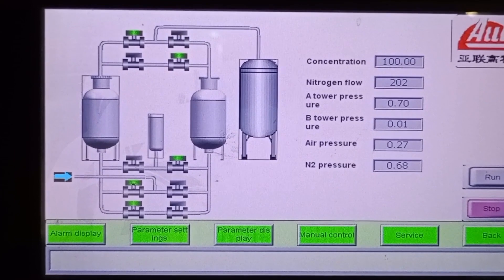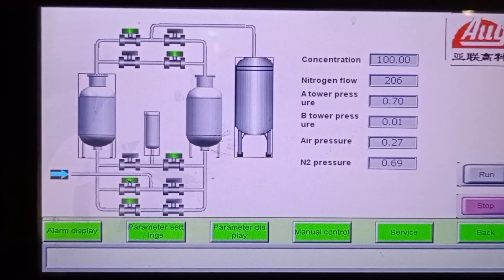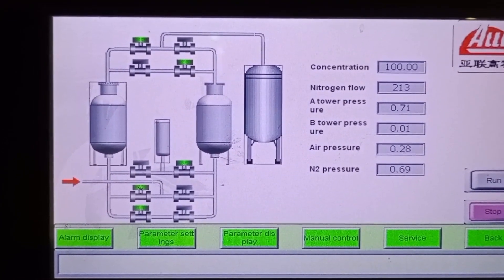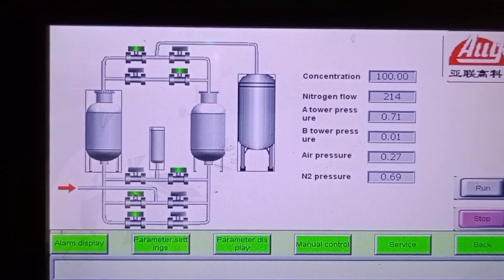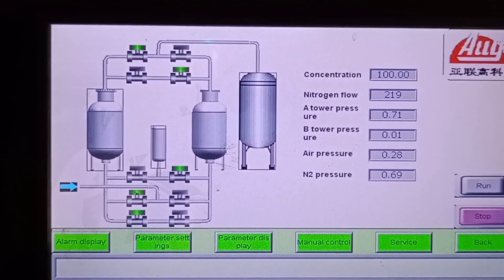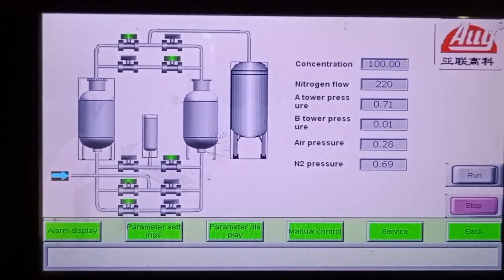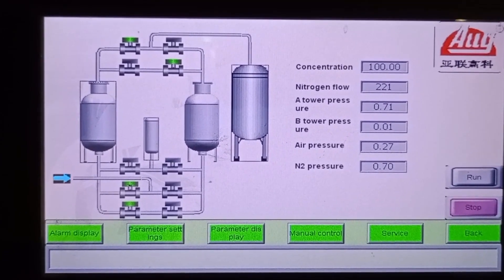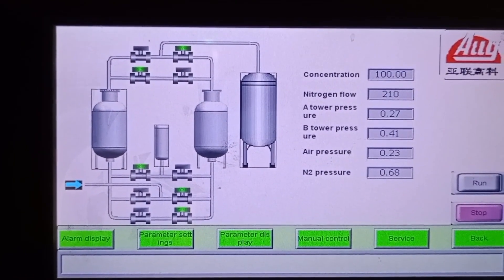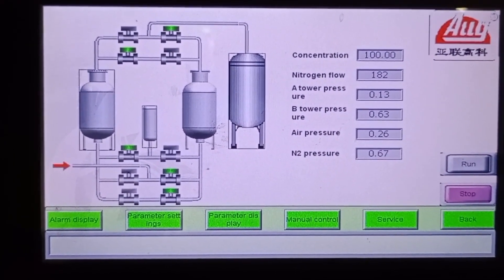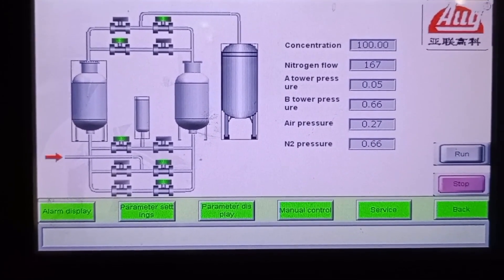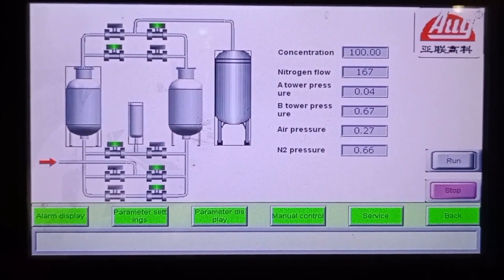Here the sequence is described. There are three sequences. First, the valves open and gas enters, and this gas is converted to nitrogen and goes to the buffer tank. Again, for a short time, four valves remain open. Then the sequence changes and the pressure swing adsorption unit changes. This is a continuous process.